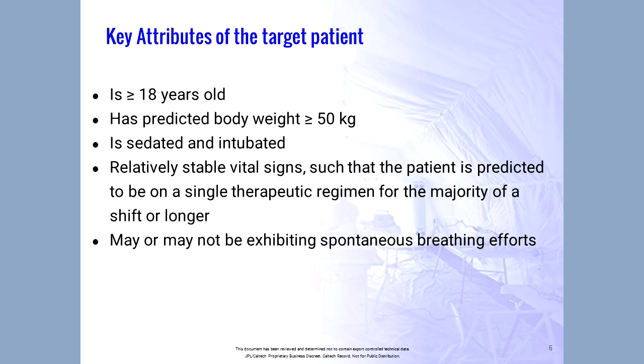In summary, the intended target patient is an adult patient over 18 years old with a minimum body weight of 50 kilograms. The patient is sedated and intubated with relatively stable vital signs, on a continuous therapeutic regimen, predominantly stable and not suffering from multiple medical situations, and can be treated with a fairly capable ventilator, but not a ventilator that would be used in a much more serious situation. The patient does or can exhibit spontaneous breathing, which was another important requirement in the design of the ventilator.